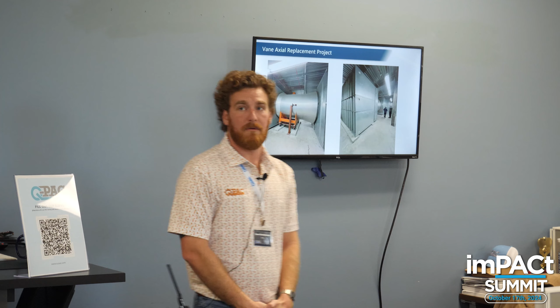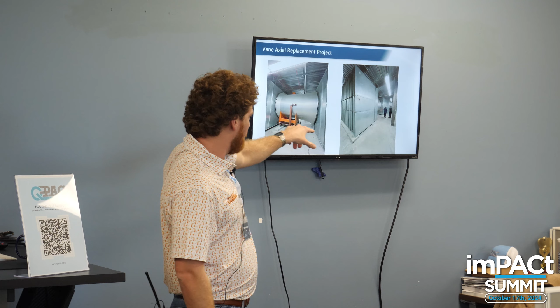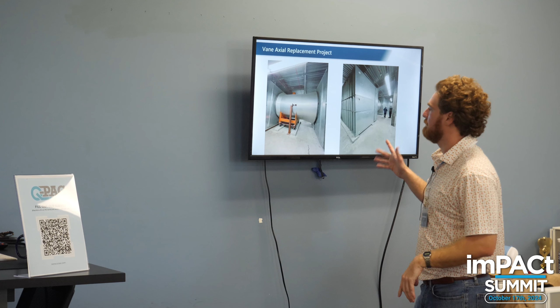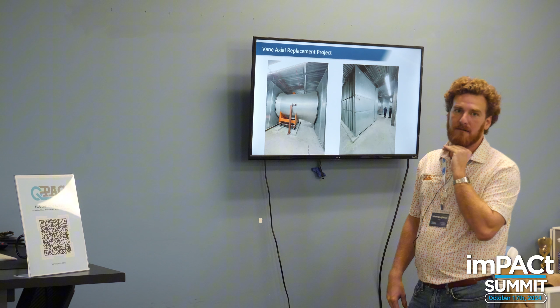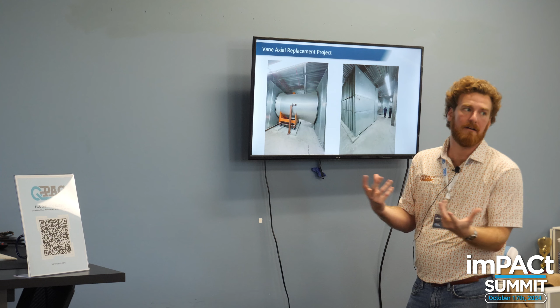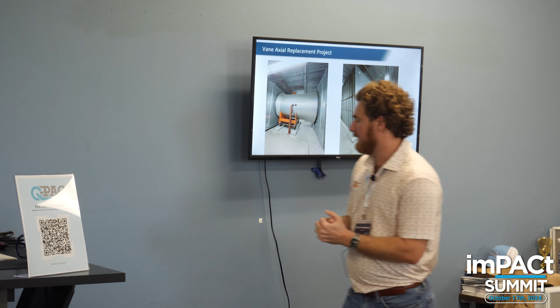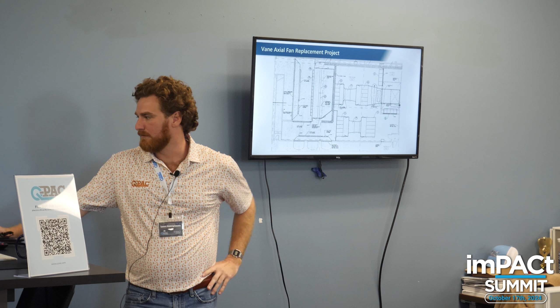It just didn't quite work out, but something to be aware of. Were they planning to blow it through that vane axial, or have a sheet metal plenum? We were going to have them demo the vane axial, and I'm 90% sure these guys are acoustic silencers. We wanted them to demo those too, but the customer in this case didn't want to get rid of them. I think maybe it just wasn't communicated how much quieter the Q-PAC fan is going to be, but either way it would have been possible, we just would have had to move this one a lot closer to that cooling coil. There were some plans we looked at, figuring out where to put it, and we said, okay, we can actually just install it right there. So that one's still in design, probably not going to go through, but we do have solutions for these vane axials.